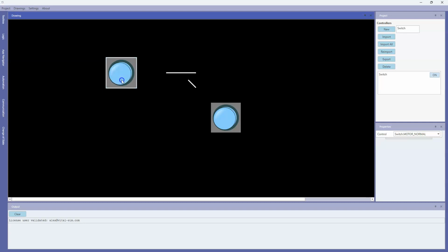So I can see clicking this doesn't do anything now. Okay, so now I've driven it out of normal position. It's in an intermediate position, and we can see that just briefly clicking either of them for up to 3 seconds has no effect. But if you cross 3 seconds, let's try that. 1,000, 2,000, 3,000. There we go. And then we can see clicking this one has no effect, and we'll just drive it back to unknown position.